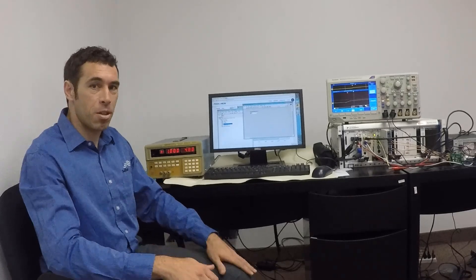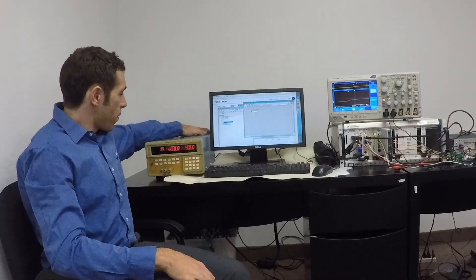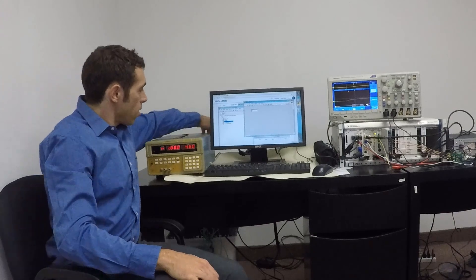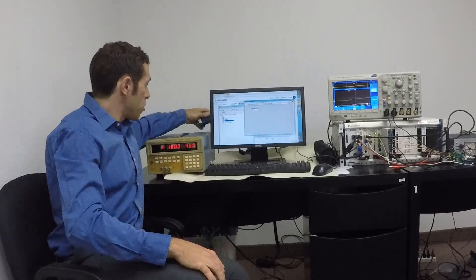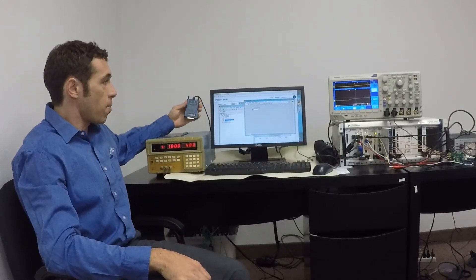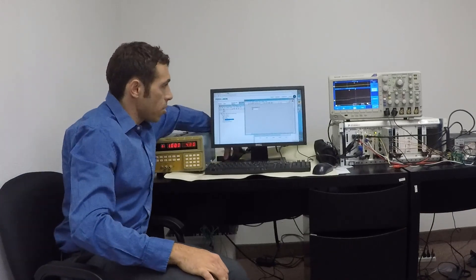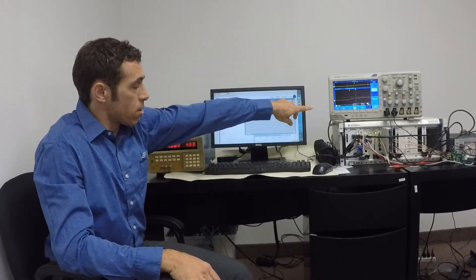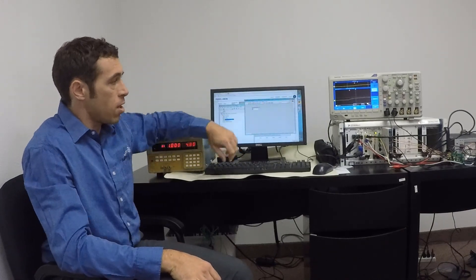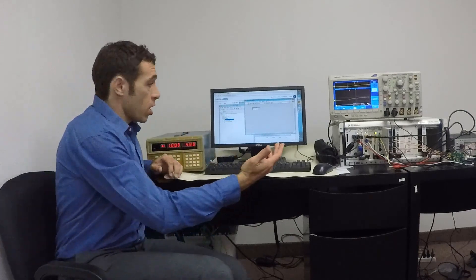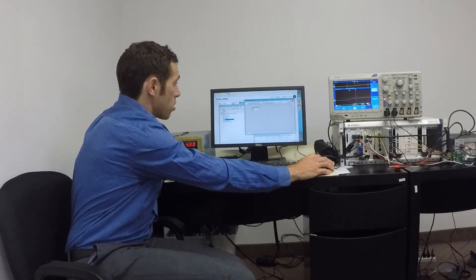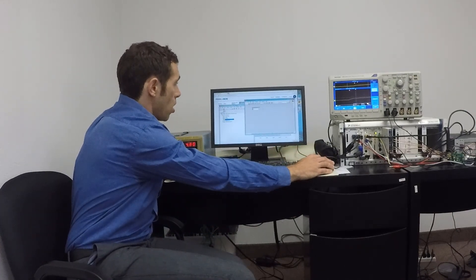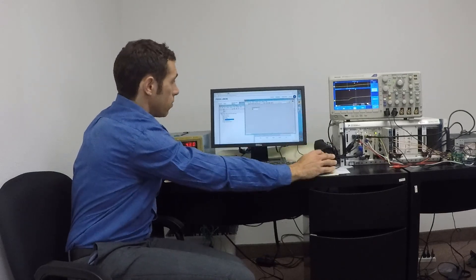Let's take a look at our instrument setup we have today. We've got a power supply connected over GPIB using an NI USB to GPIB dongle. We also have a Tektronix scope that's communicating over USB and Ethernet. Now to show that we're actually connected, I can change the range on the scope, as you can see it changing.